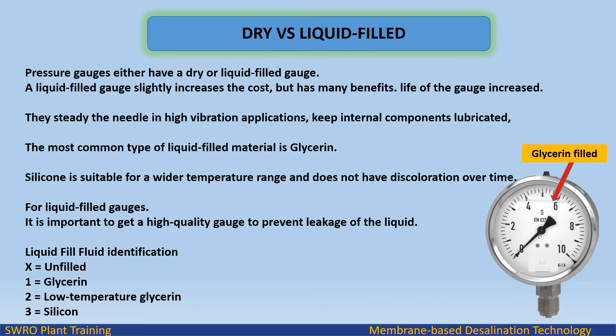Dry versus liquid filled: Pressure gauges are either dry or liquid filled. A liquid filled gauge slightly increases cost but has many benefits: increased gauge life, steadies the needle in high vibration applications, and keeps internal components lubricated. The most common liquid fill material is glycerin. Silicone is suitable for a wider temperature range and does not discolor over time.